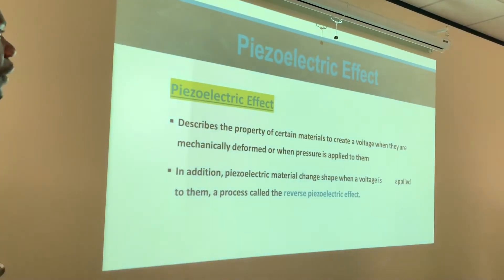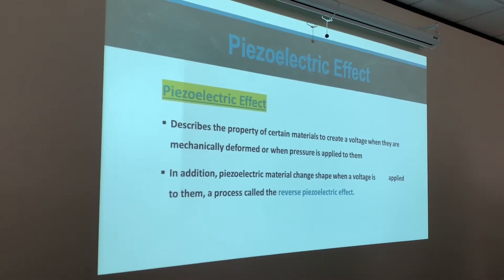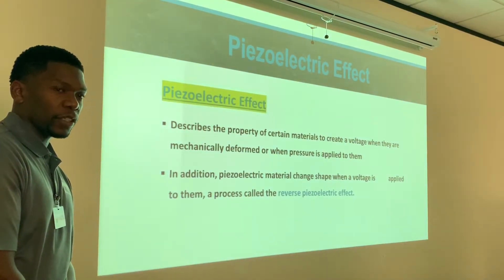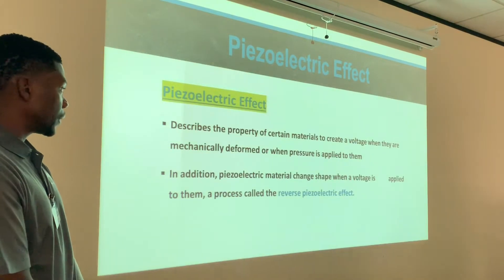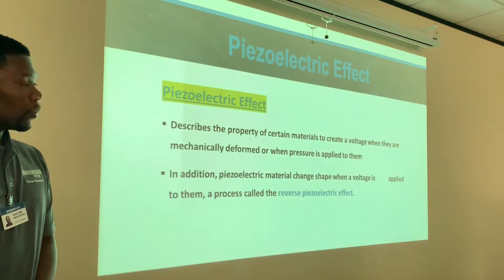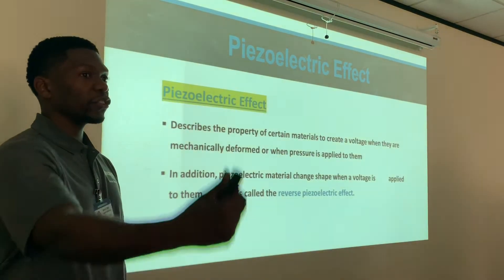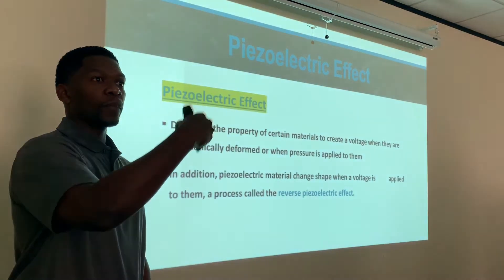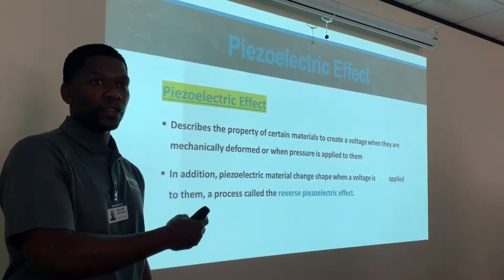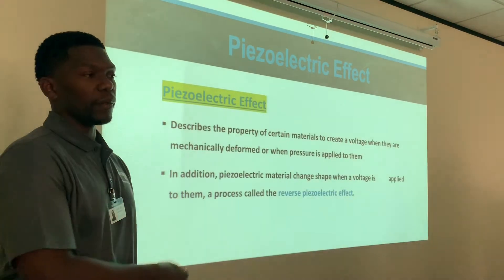The piezoelectric effect describes the property of certain materials to create a voltage when they are mechanically deformed — when pressure is applied to them. That happens during reception. Sound waves applying pressure during reception cause the PZT to vibrate. The PZT is a special material that creates an electrical voltage when pressure is applied to it — that's called the piezoelectric effect.